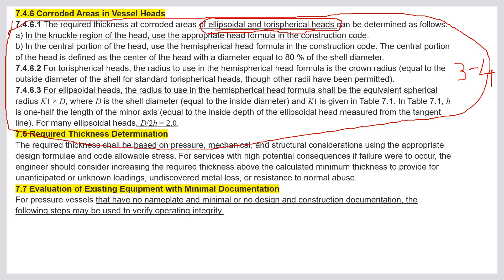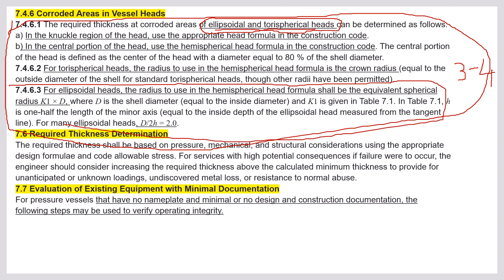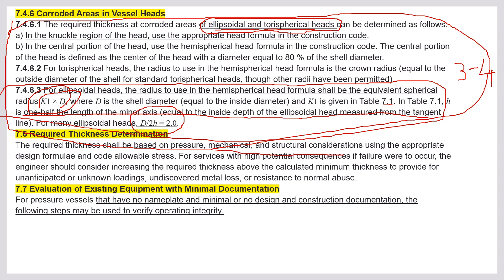For ellipsoidal heads, the radius to use in the hemispherical head formula shall be the equivalent spherical radius K₁D. The ratio D/2h = 2, where D is the shell diameter and K₁ is given in Table 7.1. H is one half of the length of the minor axis, equal to the inside depth of the ellipsoidal head measured from the tangent line. Required thickness shall be based on pressure, mechanical, and structural loading using the appropriate design formula and code allowable stress.